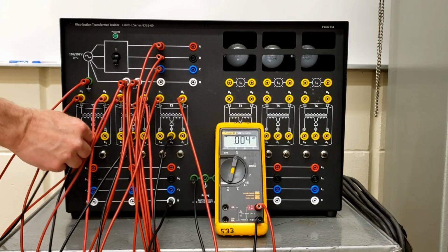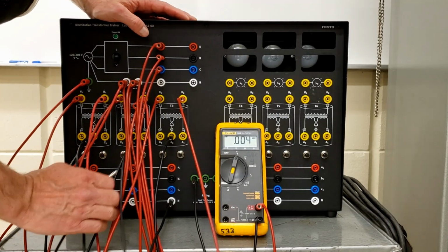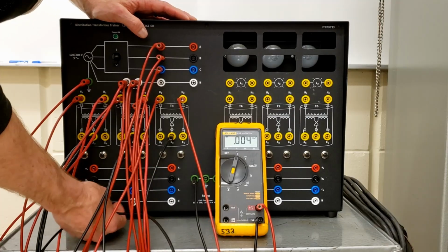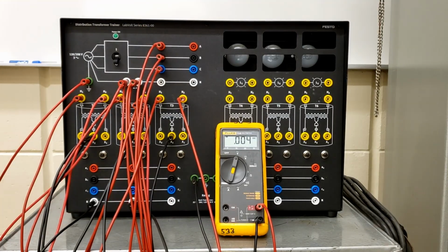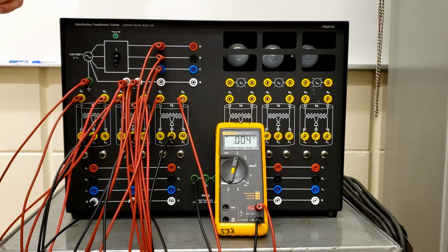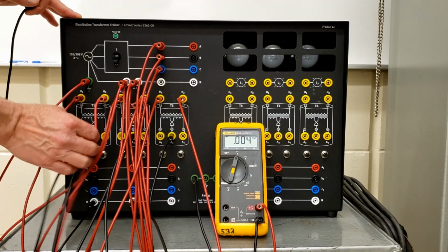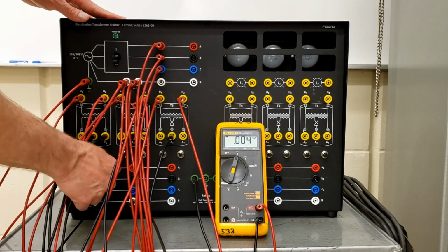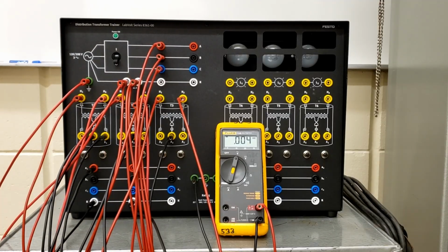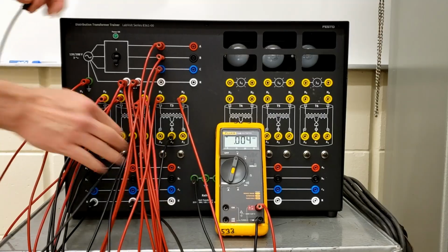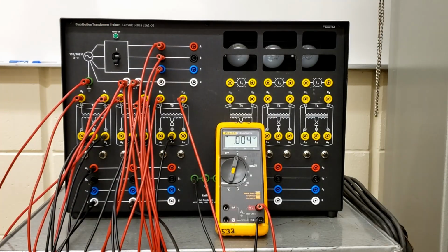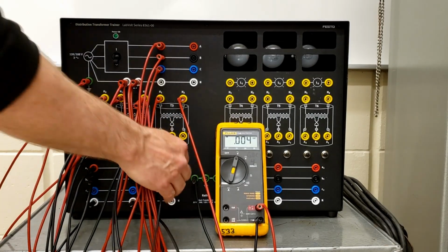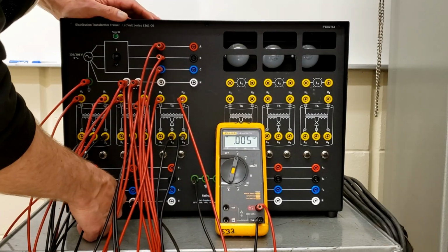Okay, X2s are tied together, feeding that neutral bus. Let's move this over so we have a place to take a meter reading. X2s are done. X1 on the primary, H1 is fed by A, so X1 goes to A because we have a 0 degree phase shift, right? So X1 is feeding the A bus here. Then we have X1 of the second transformer feeding B, and finally the last connection, X1 feeding C there.